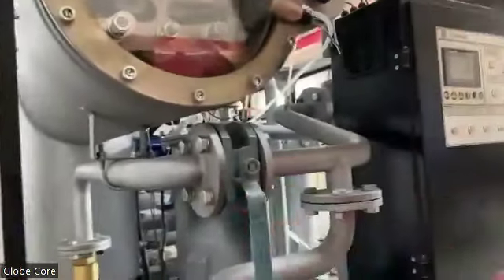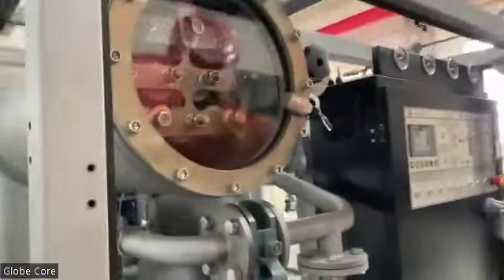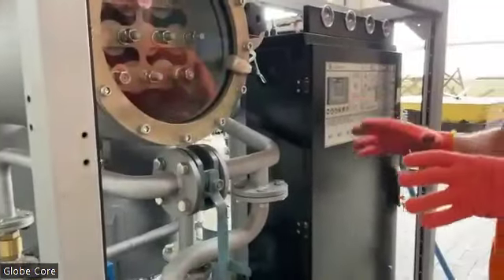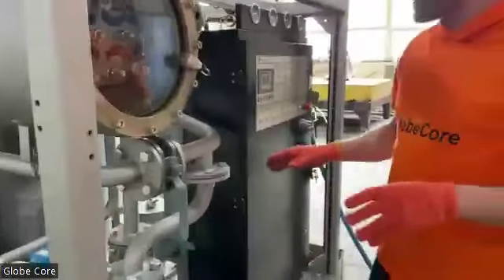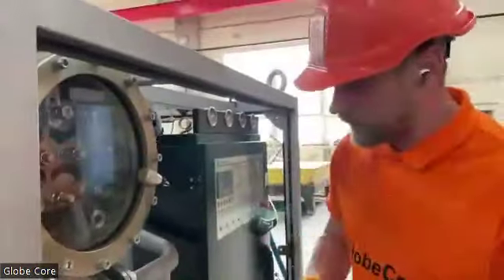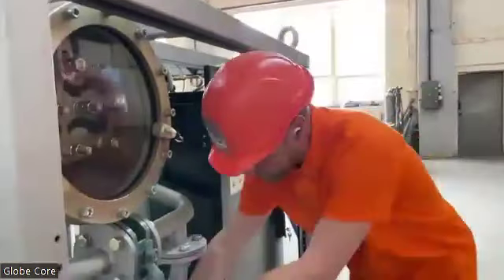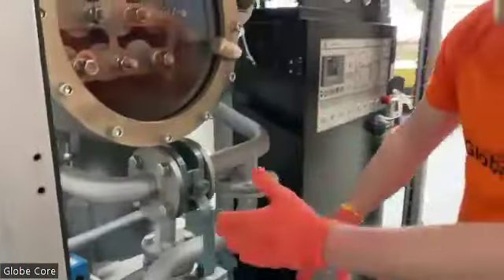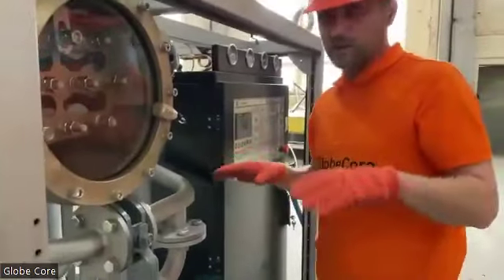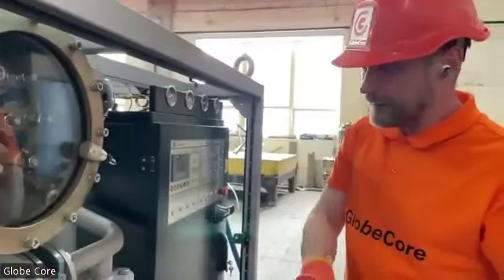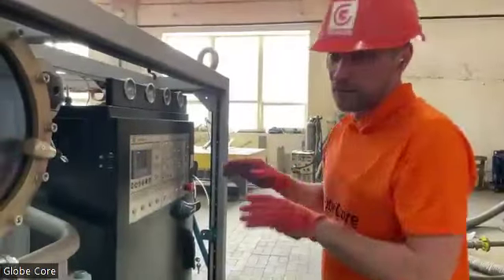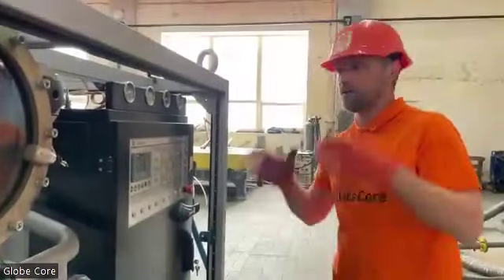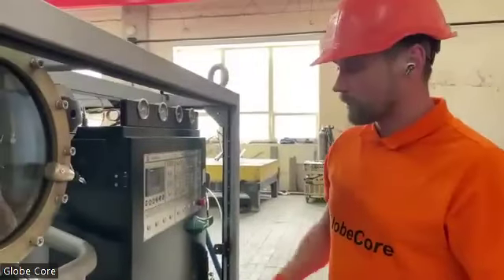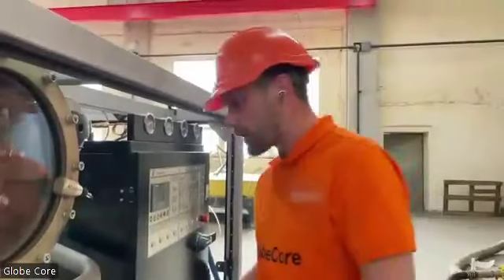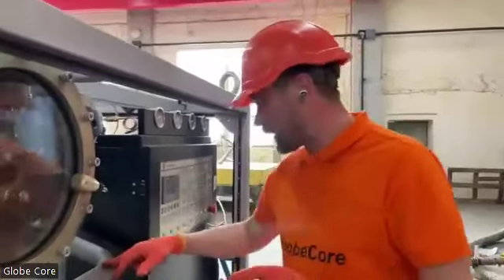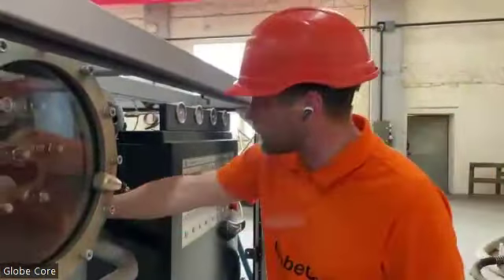What is important while operating the unit? We should balance the capacity of the inlet and outlet line. So with these two valves, we adjust the capacity of the pumps and balance the system. So the flow on the inlet is equal to the flow on the outlet, and this is the right way to work with this unit. It is quite important. So through this valve, oil goes to the second fine filter.